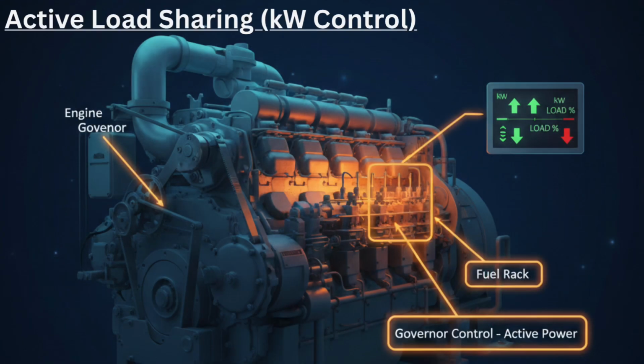Active load sharing, kW control. Active load sharing controls real power, or kW. This is controlled by the engine governor. If one generator is taking more kW, we reduce its fuel input slightly. If another generator is taking less kW, we increase its fuel input. In automatic systems, load sharing module adjusts fuel rack automatically. The governor maintains equal speed and balanced load. If active load is not shared correctly, one generator may become overloaded. Reverse power trip may activate. Engine stress may increase. Correct governor tuning is very important for smooth kW sharing. Remember, fuel controls active power.